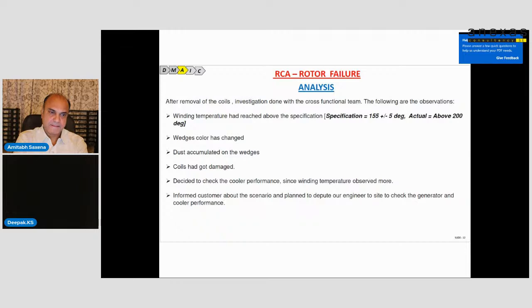Now I am coming to the analysis part. After removal of the coils, the investigation was done with the cross-functional team. The following are the observations. This is very, very important. We observed the winding temperature had reached above the specification. The specification for the winding, for this class of insulation, is 155 degrees plus or minus 5 degrees. Actually, it has gone to about 200 degrees.